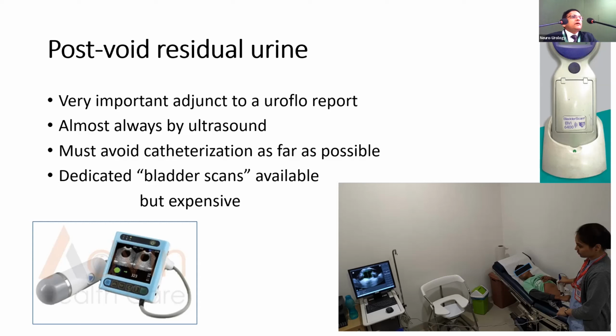Then post-void residue is obviously an essential part of your uroflowmetry measurement. It could be either a dedicated bladder scanner. There are multiple imported ones available, but these are prohibitively costly, or now some Indian machines are also available. Or if you have a small ultrasound machine in your setup for multiple purposes, you can use the same machine for measuring the post-void residue. I would emphasize here that unless you are planning to catheterize the patient for some reason, please don't use catheters for measuring post-void residue. That would be really invasive, unless it's really necessary.